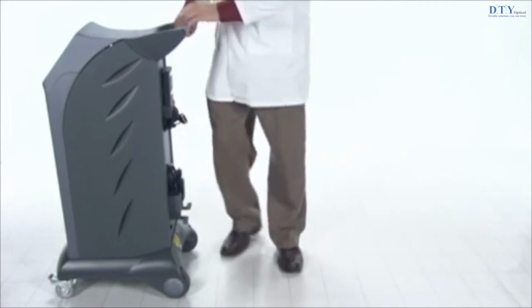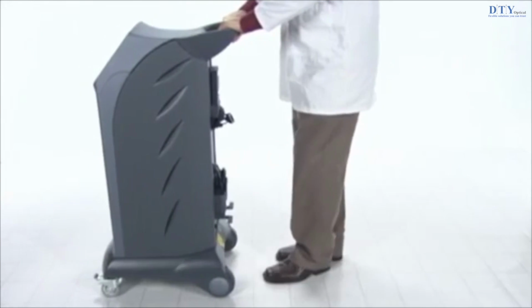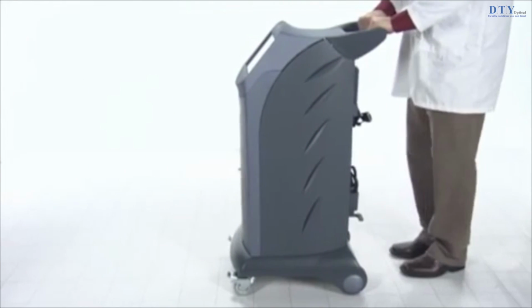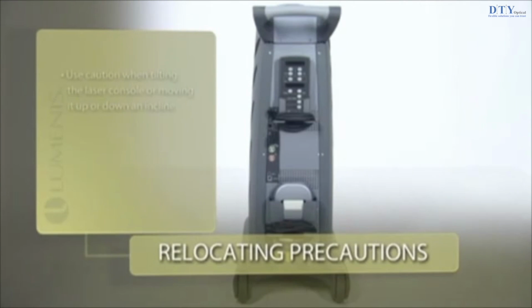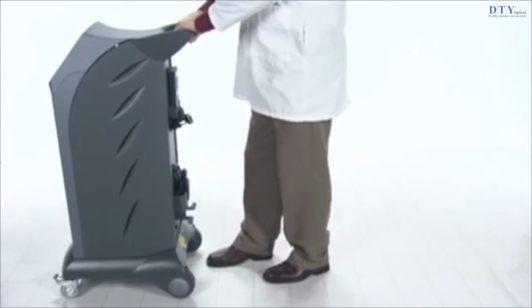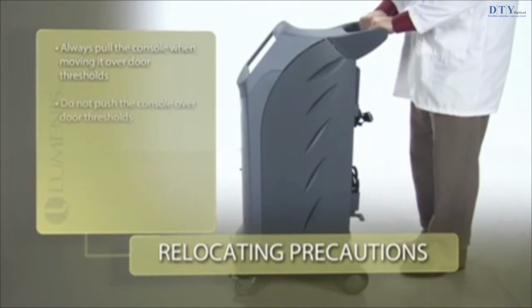If you need to move the Vision One laser, remember, always use the laser console handle when repositioning the system. As with any heavy equipment, use caution when tilting the laser console or moving it up or down an incline. For optimum safety, use a second person when moving up or down a steep incline. Always pull the laser console when moving it over door thresholds. Do not push the laser console over door thresholds. Do not move the laser console rapidly over uneven surfaces. Doing so may damage the equipment.